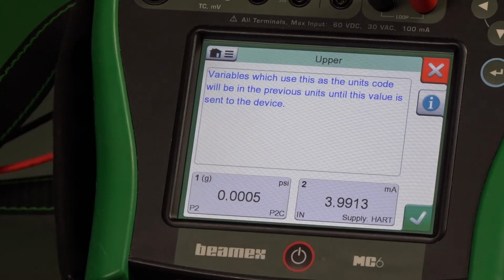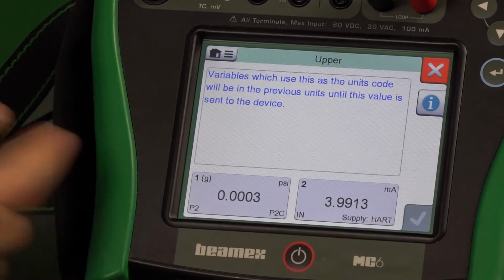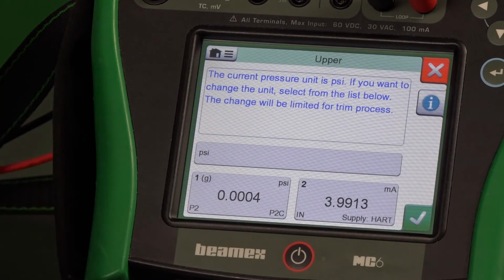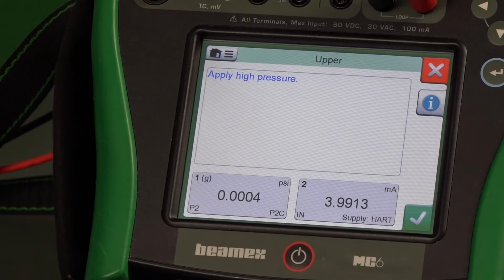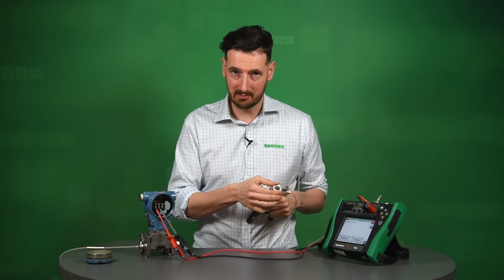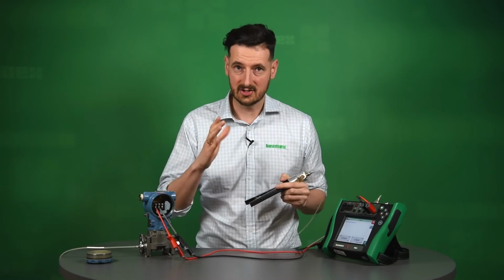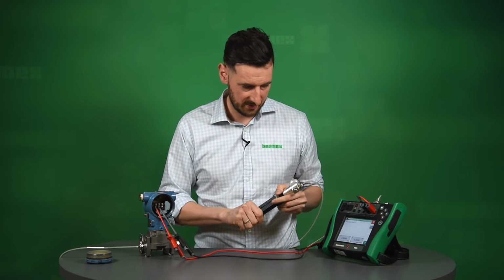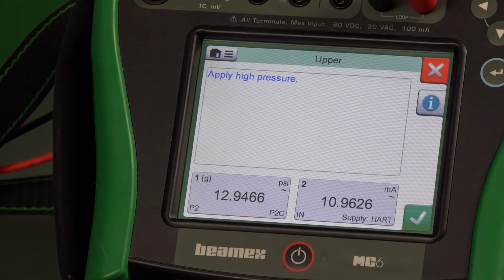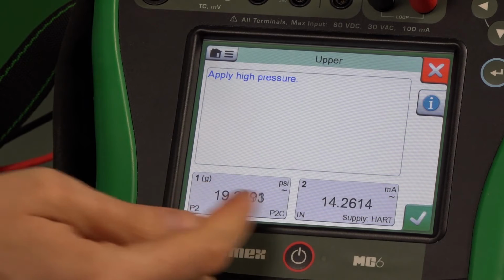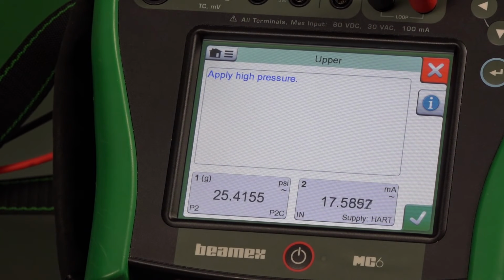So it gives us a warning. Yes, it tells us again some information. It's asking us what sort of units we want to have. We say PSI, it's fine. And it's asking us right now to apply high pressure. Now, this is 30 PSI. So we need to go there or thereabouts, to 30 PSI. You can see that the input, the pressure, and the 4 to 20 are changing. So try to get as close as possible to 30 again. So we can actually trim that. Right, okay. We're more or less there.